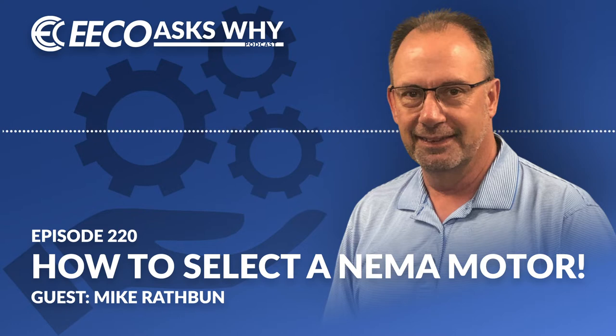So I think there's some obvious information in there that probably most people in industrial maintenance or in engineering are comfortable with. If I have to replace a given motor in an application, I need to match up things such as the voltage rating of that motor. Obviously, we don't want to operate a 460 volt motor on a 2300 volt distribution system. The speed of the motor, obviously, so that it matches the application, and the horsepower requirement so that we can deliver enough force to drive the application. I think most people are comfortable with that.